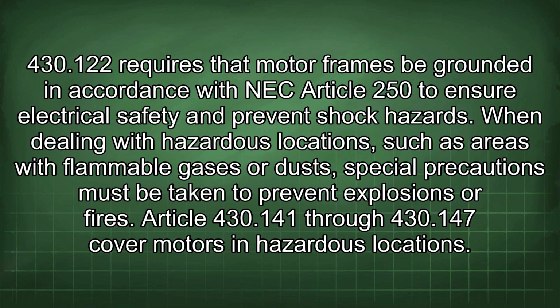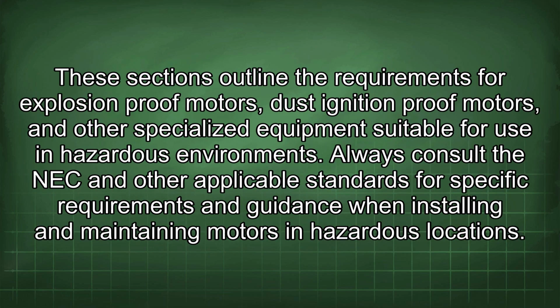430.141 through 430.147 cover motors in hazardous locations. These sections outline the requirements for explosion-proof motors, dust ignition-proof motors, and other specialized equipment suitable for use in hazardous environments.